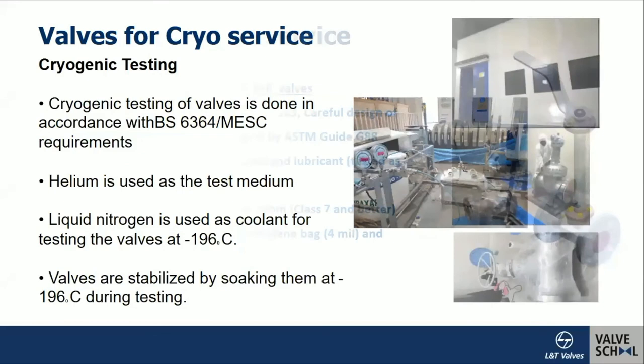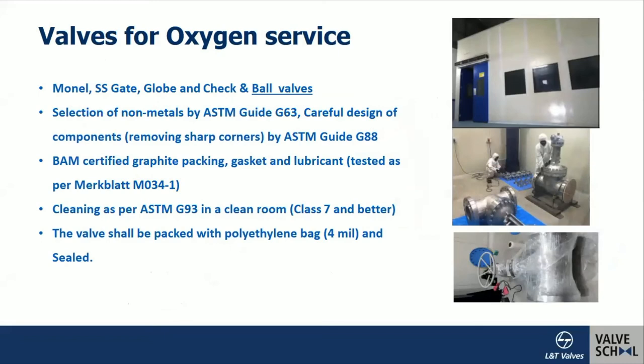For oxygen service, valves must be assembled in a clean room where dust particles are not more than 5 microns and quantity is less than 3,000 — meeting ISO Class 7 (or 10,000 class) requirements. Non-metals are selected per ASTM guidelines, and BAM-certified graphite packing, gaskets, and lubricants are required.